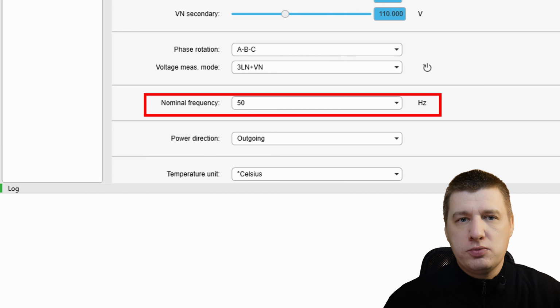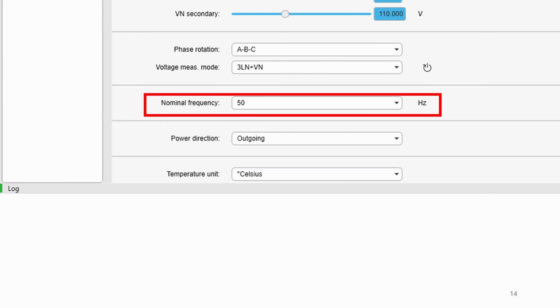This setting isn't just for the clock. The relay uses the nominal frequency as a baseline for its measurement functionality. If this value is set incorrectly, your frequency-based protection like underfrequency or load shedding will be directly affected. The P5 is precise, offering a frequency measurement accuracy of up to 0.1 Hz, while the nominal setting is 50 or 60 Hz. It can even determine the frequency using current signals if the voltage drops below 15% of the rated value.